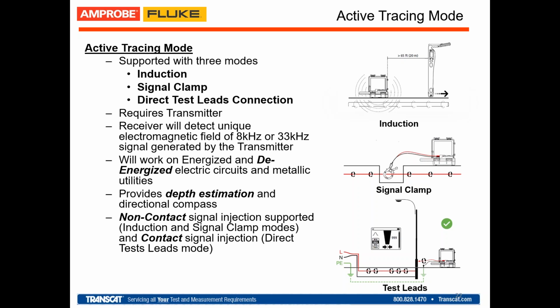So just by using the clamp, you connect it to the transmitter, and if you have access to the cable of the circuit, whether at a panel or a cabinet, you connect the clamp to the cable, go straight to the transmitter, and the transmitter induces the signal through the clamp to the cable. And the most accurate mode, and the most popular one with underground locators historically over the last 20 years, is direct connection. You take the transmitter, you connect the test leads, and then the test leads go into an open conductor access, and that will generate the signal directly on the conductor.